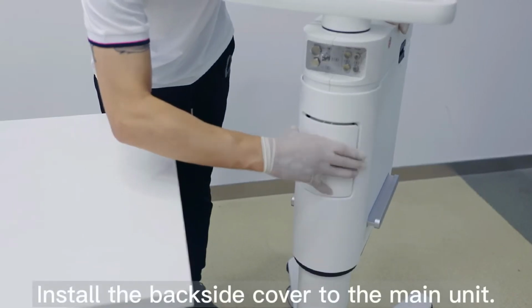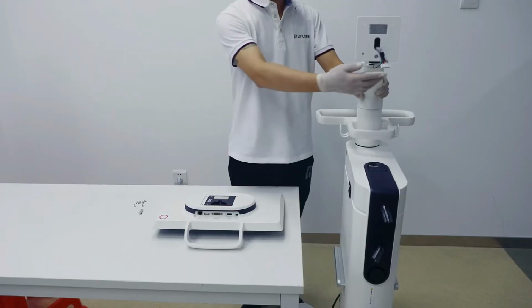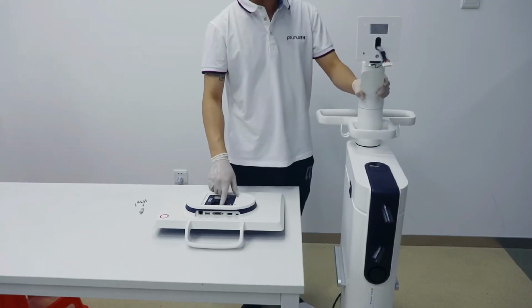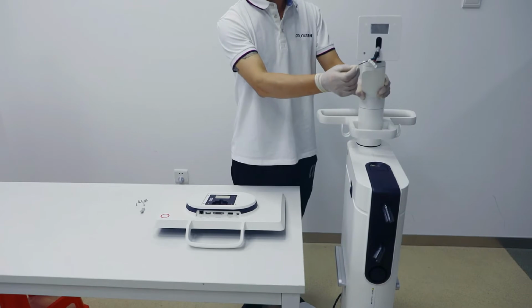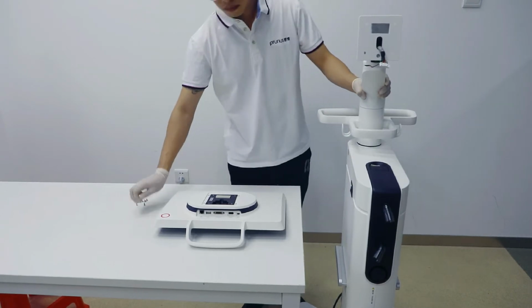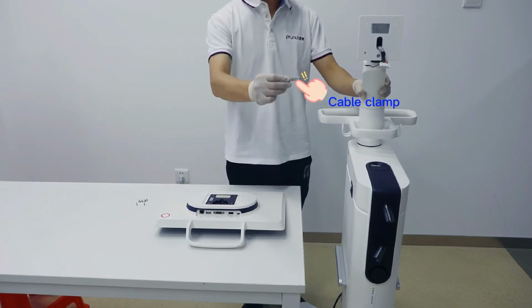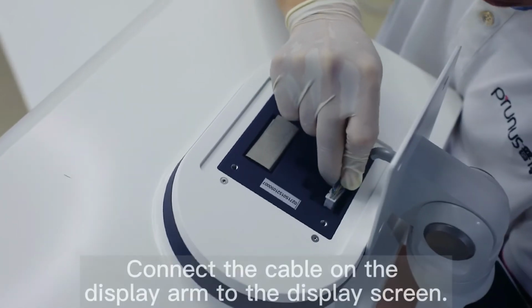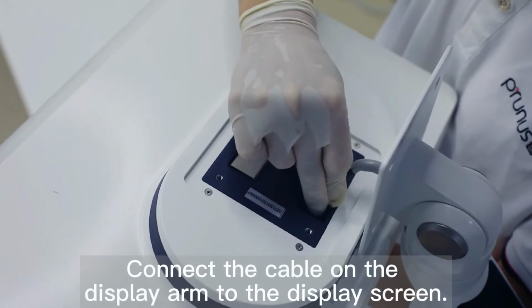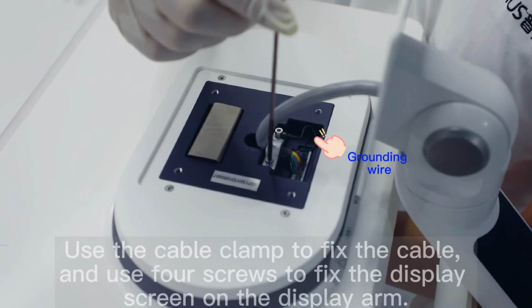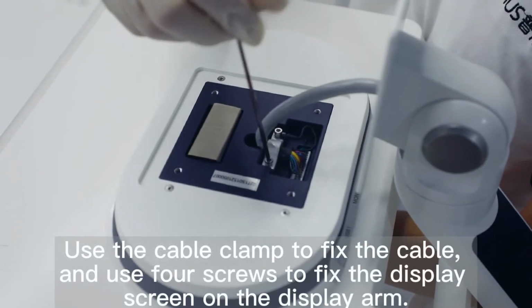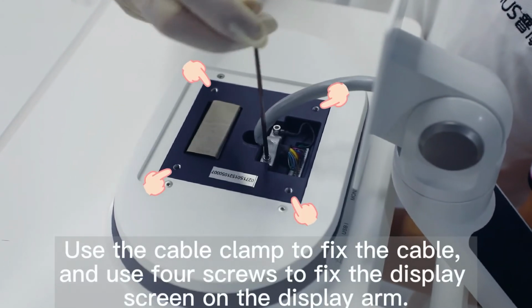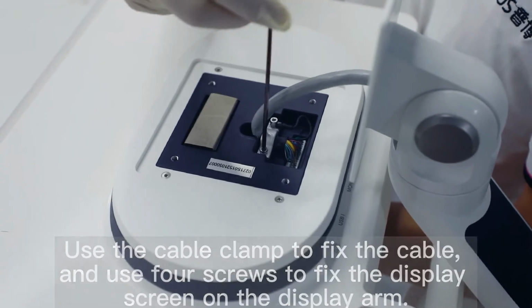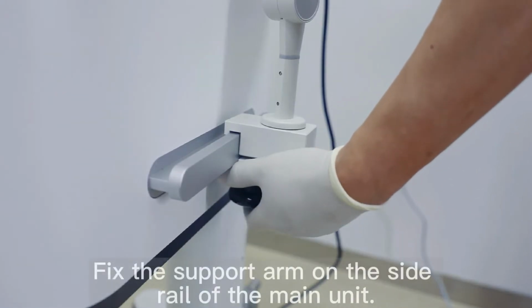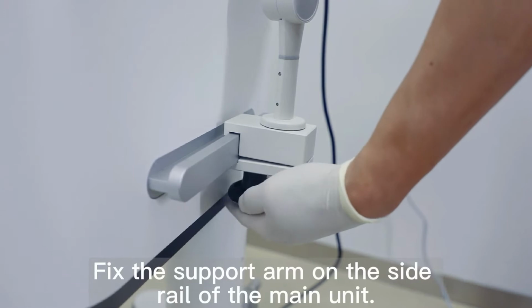Install the backside cover to the main unit. Connect the cable on the display arm to the display screen. Use the cable clamp to fix the cable, and use 4 screws to fix the display screen on the display arm. Fix the support arm on the side rail of the main unit.